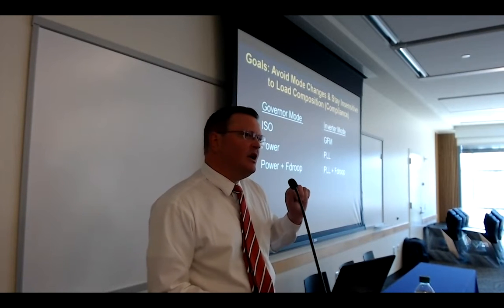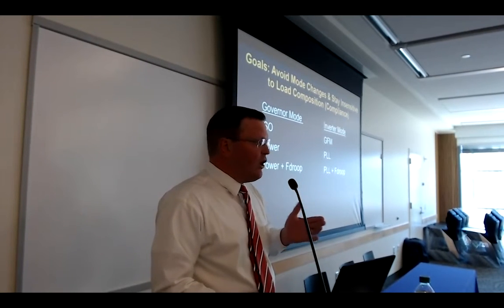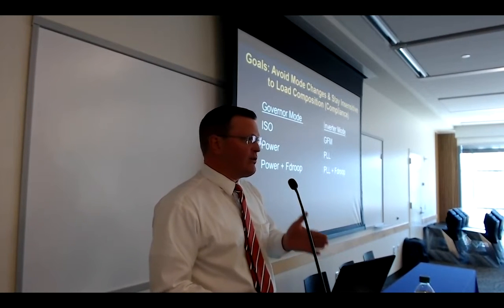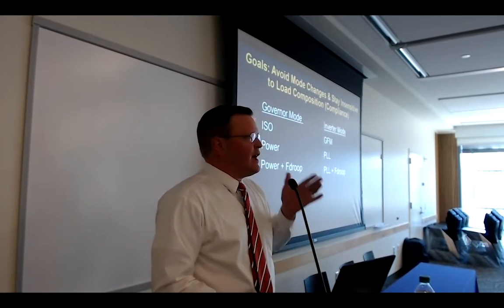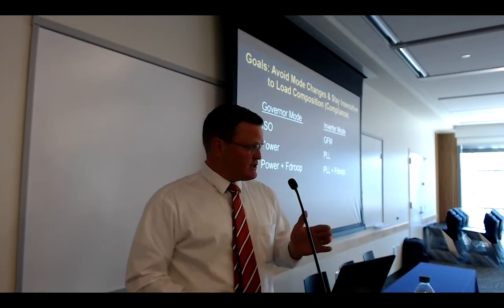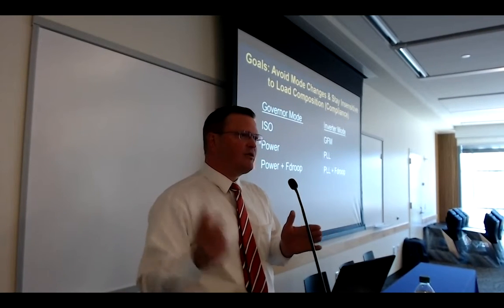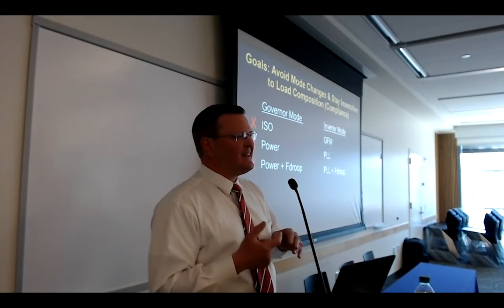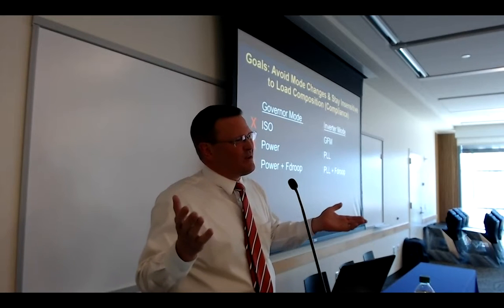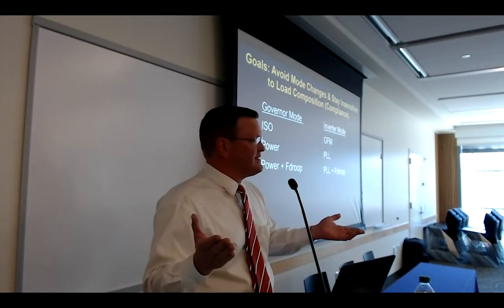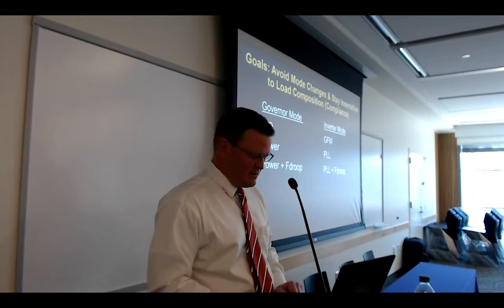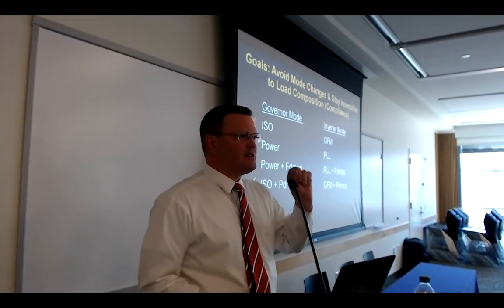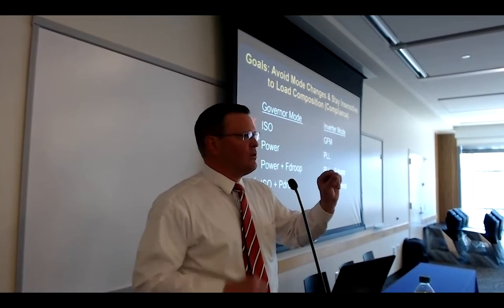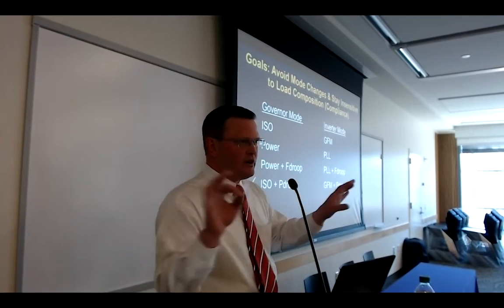The next thing, when we start to evaluate what sort of droop behavior is best served in a turbine for frequency regulation, we know from absolute certainty, over 100 years of experience, that a power control loop, such as in a steam turbine facility, with a small frequency measurement for droop, is meh. It sort of complies, it's not great, it's a real problem, as we've proven many times. The best is a stiff frequency control loop with a power droop, period, absolutely no question.